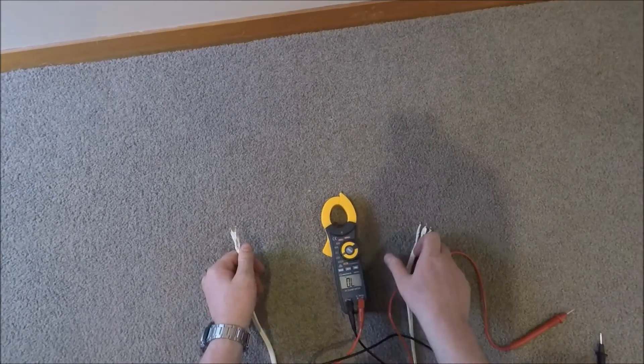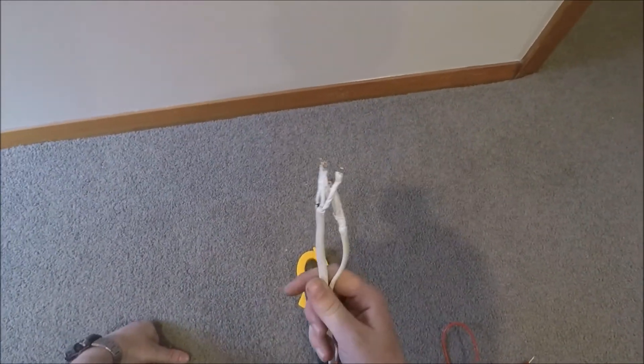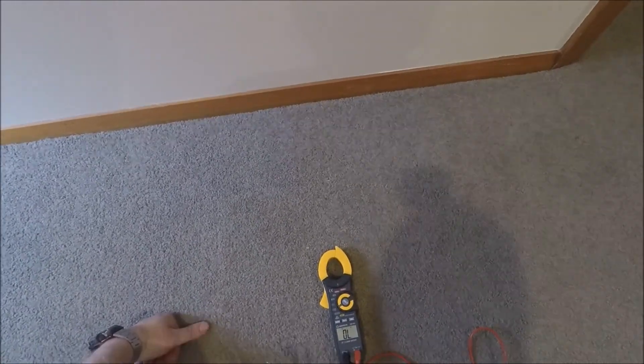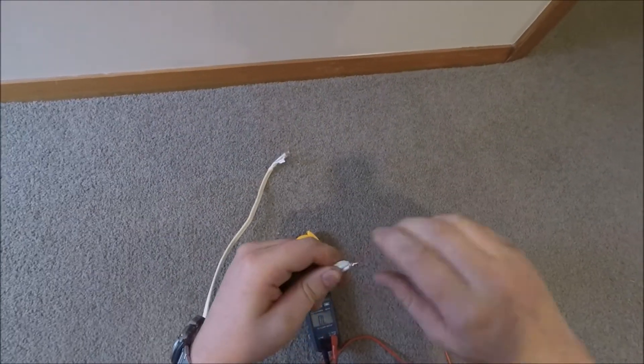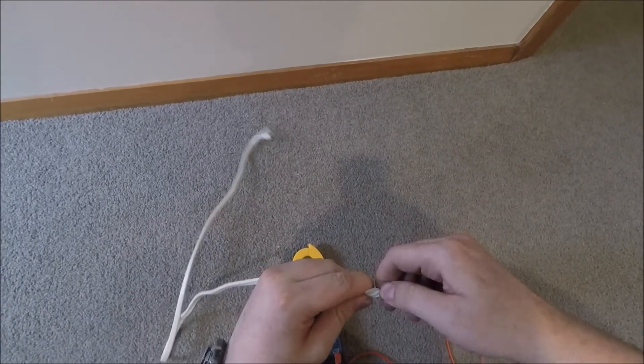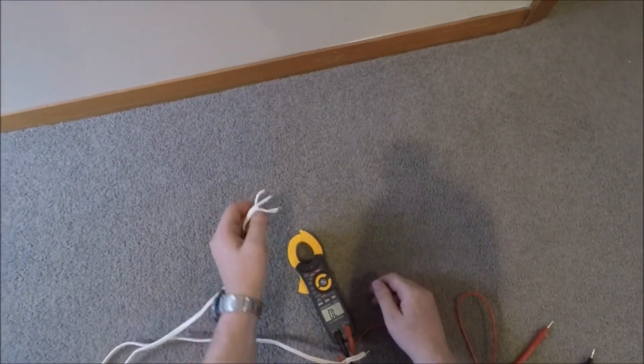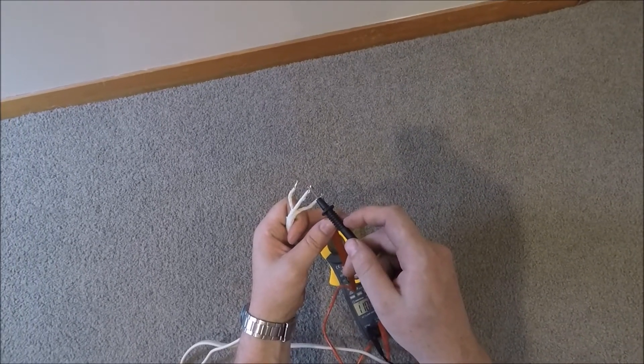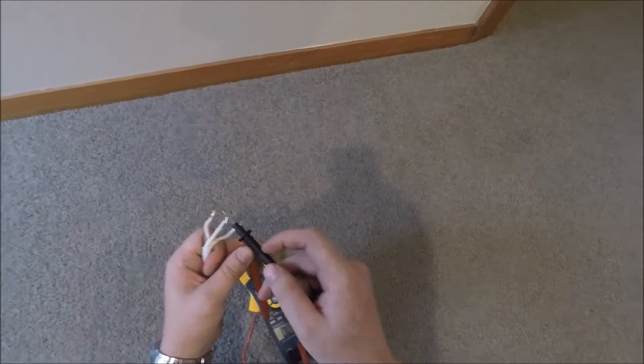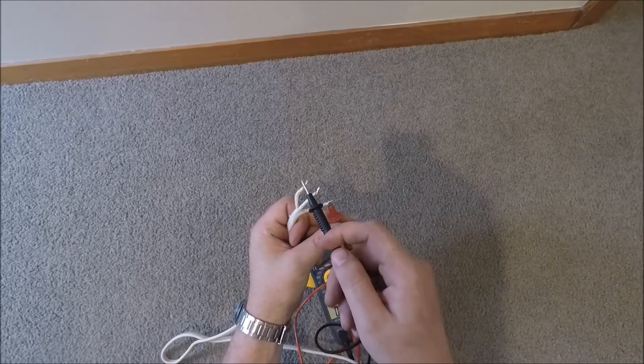What's handy is this cable's short. You might be using it on these kind of cables in cars, but for a house the cable's generally 30-odd meters long. If it's an old cable it could be broken, so this is another trick we do. We go to one end of the cable, twist all the cores together, and then go to the switchboard, put one end on the earth and then one end on one of the phases. We can find that cable really fast. One end would go on the earth bar and we'd just go through the bottom of the circuit breakers to find what cable's got a short on it. Obviously the power will be isolated.